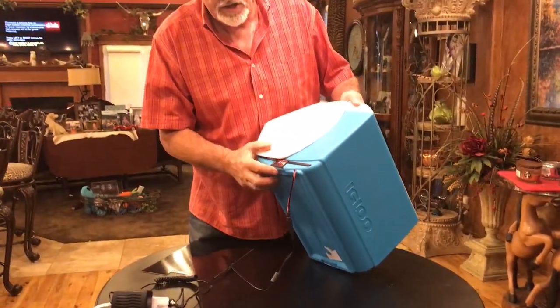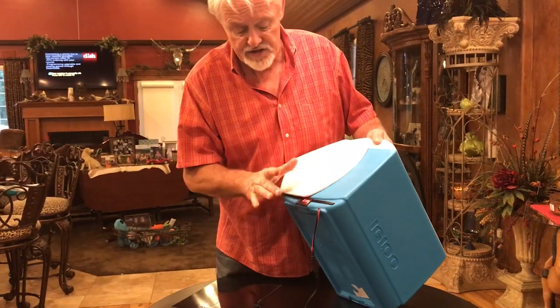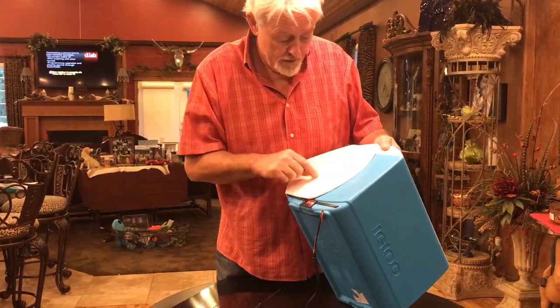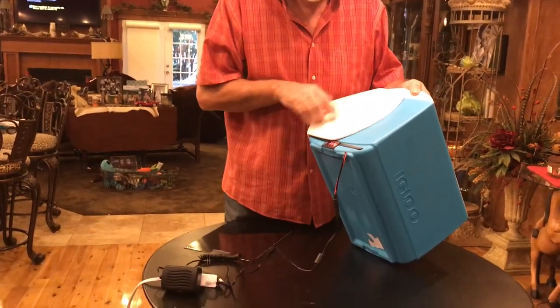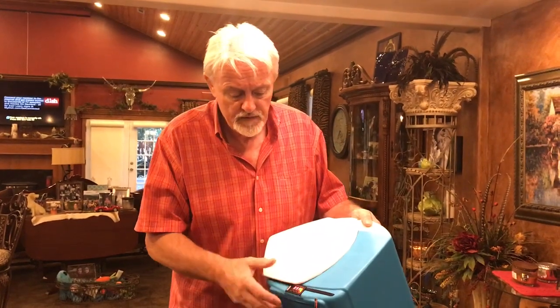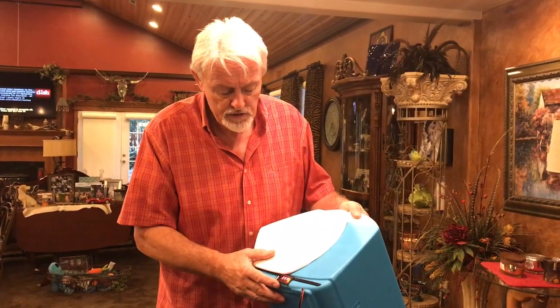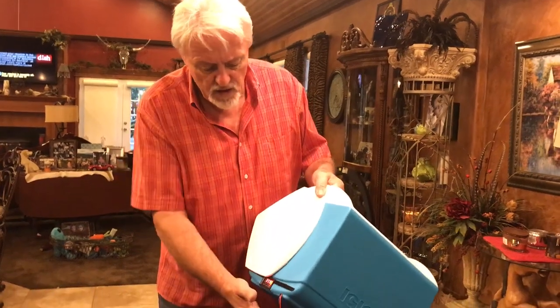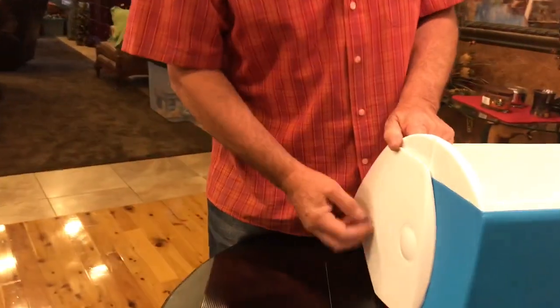So the old system, you could change it for both Fahrenheit or centigrade. These thermostats I've got now are more accurate. That's why I've moved to this thermostat. And it is a centigrade thermostat. And there will be a little stick-on chart on here that shows you what Fahrenheit and centigrade are equivalent to, just in case. Because we're in America, we're used to Fahrenheit. In Europe, we're used to centigrade. So 40 degrees centigrade, 102, 103 degrees Fahrenheit, perfect temperature. But there will be a chart there. There will be a chart stuck on front of it, yes.